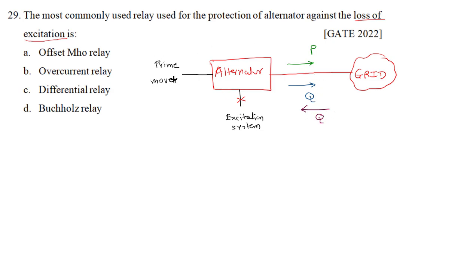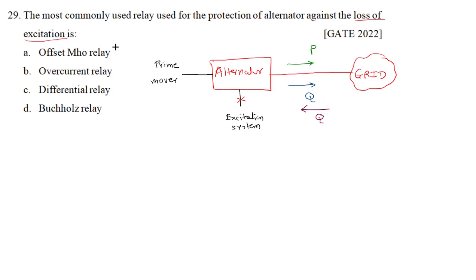As the prime mover input is intact, the alternator will still supply active power. So whenever there is a loss of excitation, the alternator supplies active power but takes reactive power from the grid. During this condition, its impedance changes, and we use the offset mho relay to detect this condition and provide protection against loss of excitation.